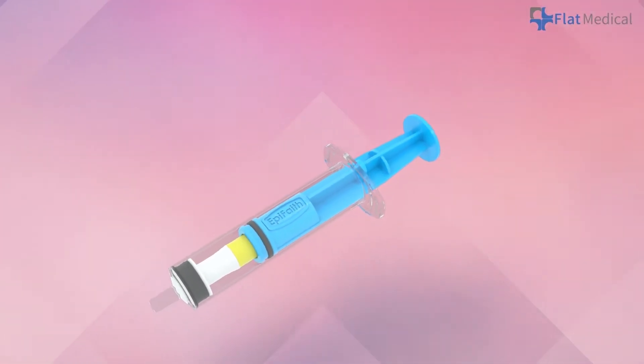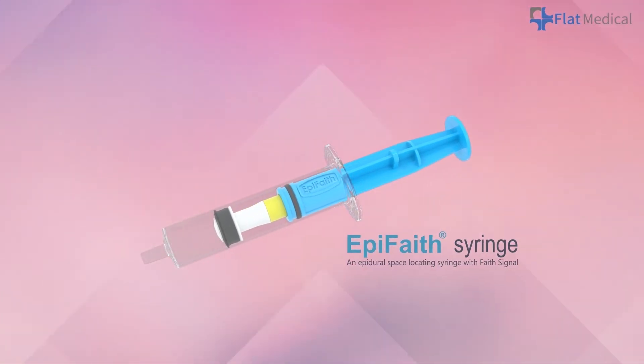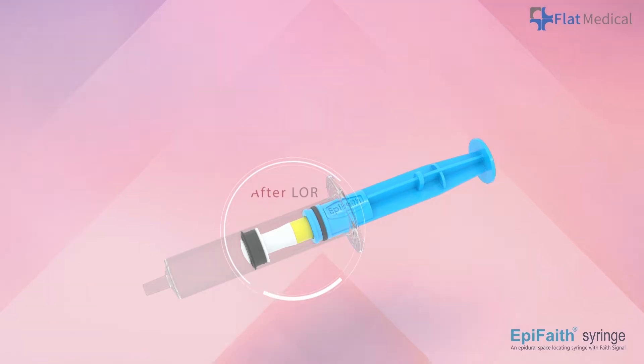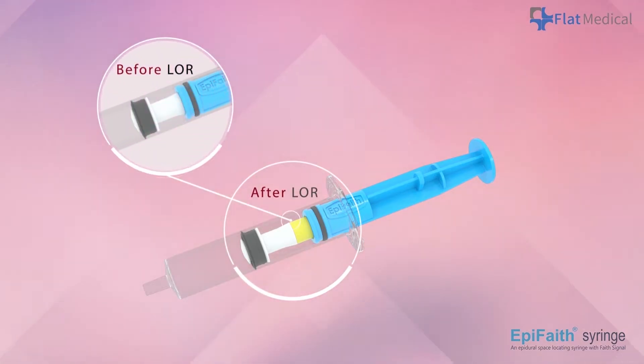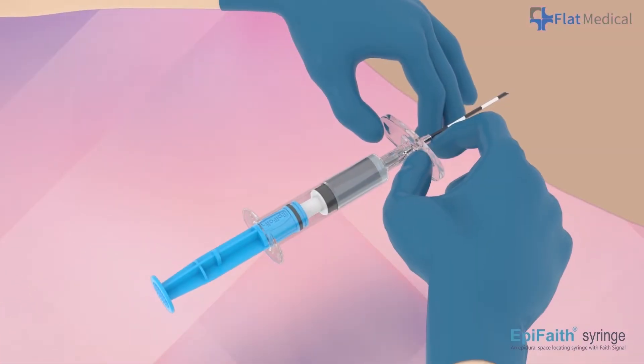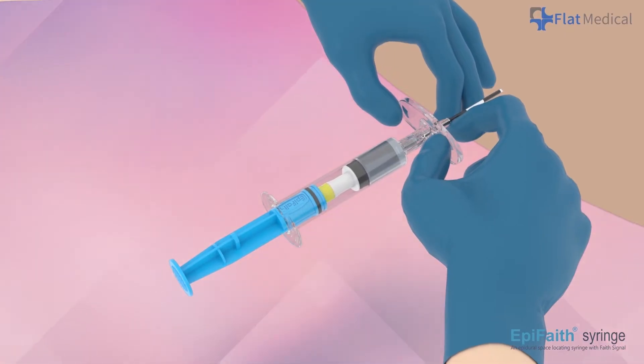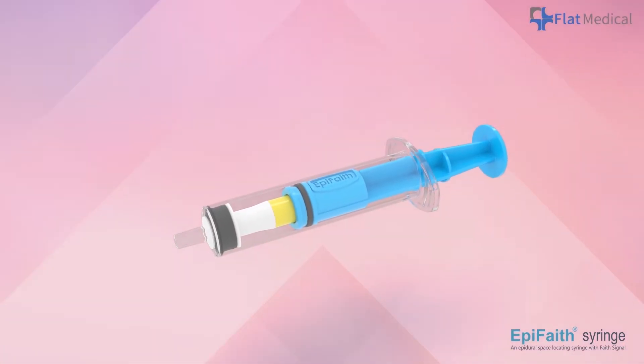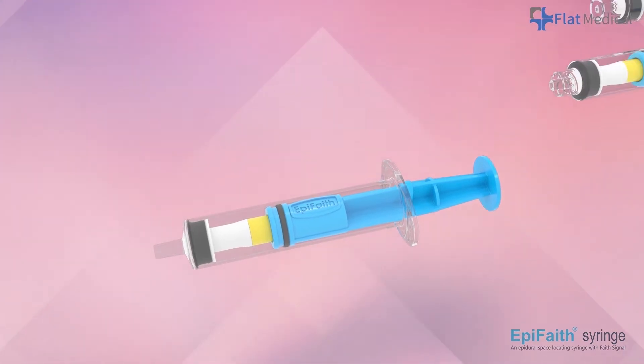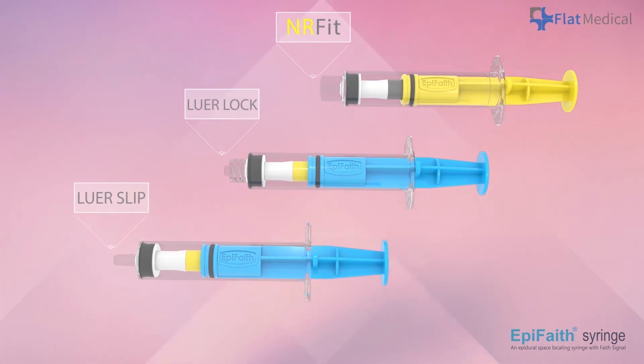The EpiFaith syringe is a compact and reliable tool designed for epidural localization. It features a unique automatic and continuous pressure detection mechanism that provides a clear visual signal to indicate the needle's position. Additionally, the device enables operators to use both hands to advance the needle for precise control. The EpiFaith syringe offers three connector options to accommodate various needle connector types. Please select one according to your preference and local regulations.